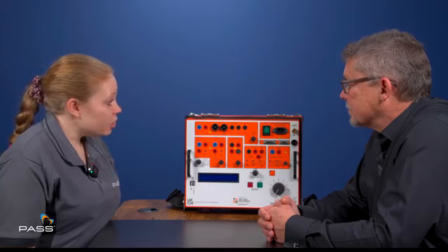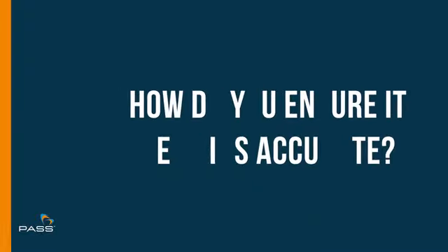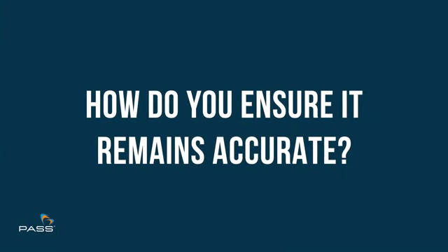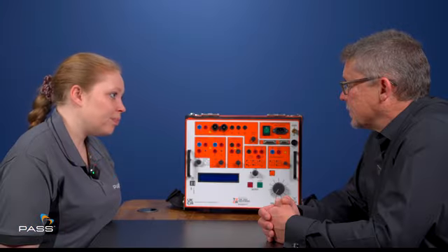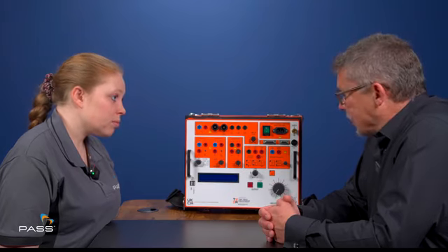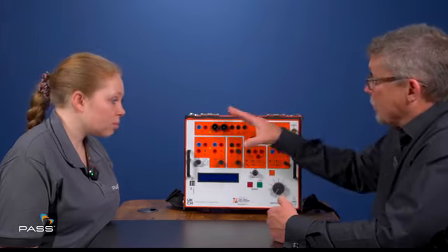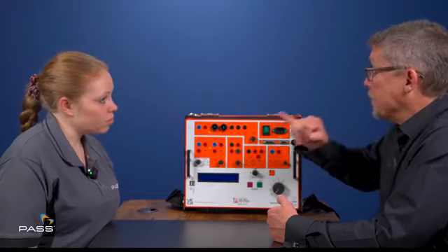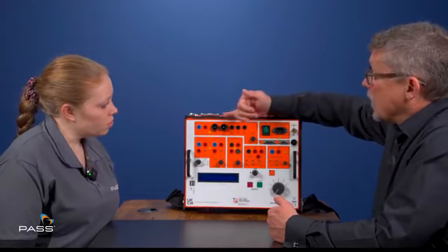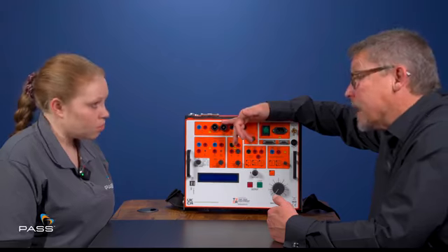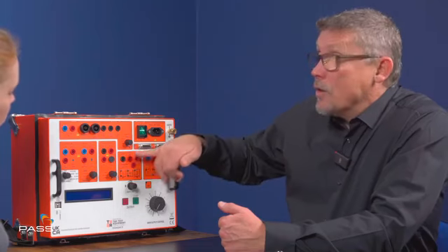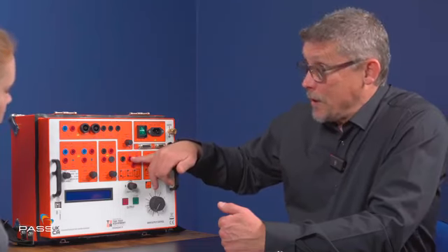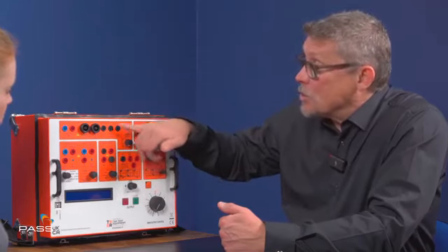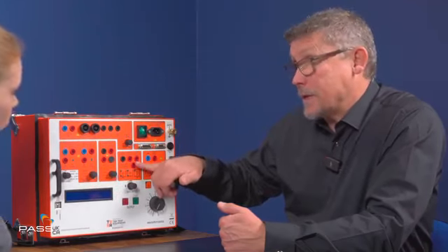So obviously accuracy is critical. How do you ensure that the secondary current injection tester remains accurate? Well, from the factory when they're built, they're calibrated, and every single one of these channels is calibrated. The important ones being the voltage and the current coming out of there is metered correctly. The voltage, the current, the frequency, and the phase angle shift between these two is metered correctly.